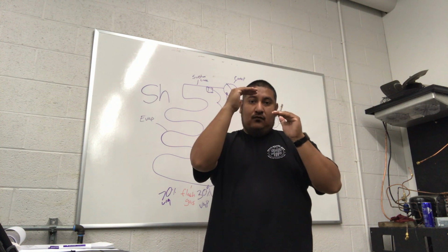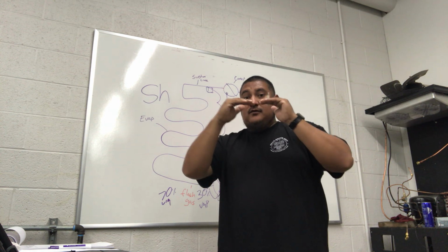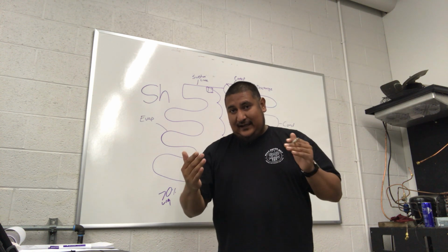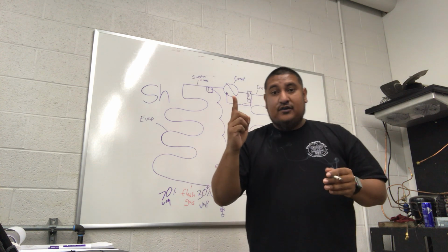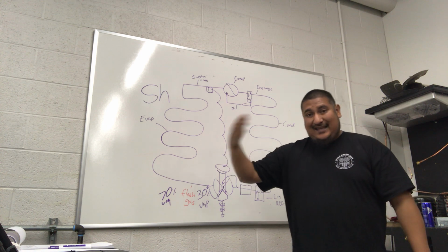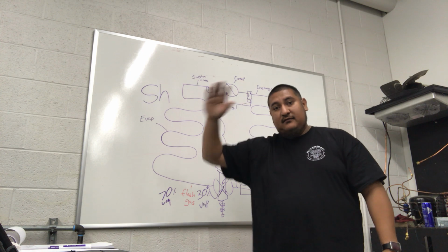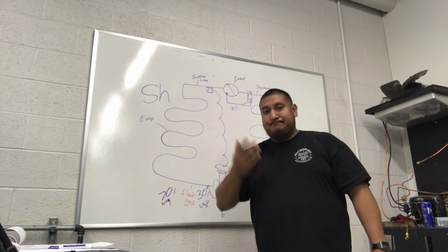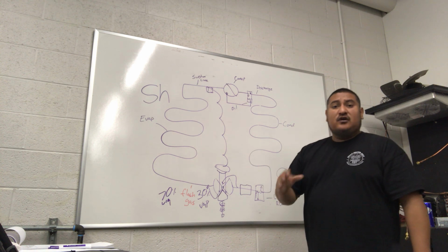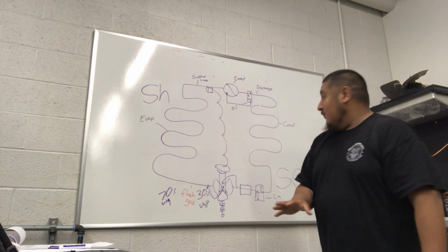If you push it 1 degree above that 60 degrees, you have 1 degree of superheat. If you drop it down 1 degree from that 60, you'd be at 59, now you're going to have 1 degree of subcooling, right? So that's the definition of superheat and subcooling. It's just push it above its saturation temperature, you're superheating. Drop it below its saturation temperature, you're subcooling, right? Now, superheat and subcooling are very critical to our trade, right? You guys have to understand that from the get-go, right?